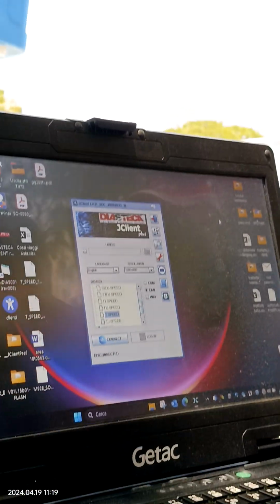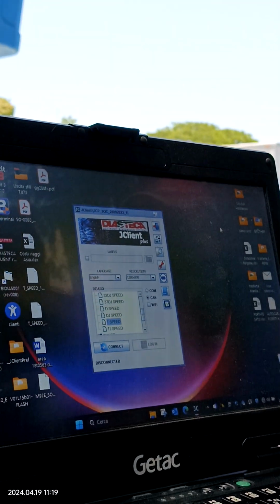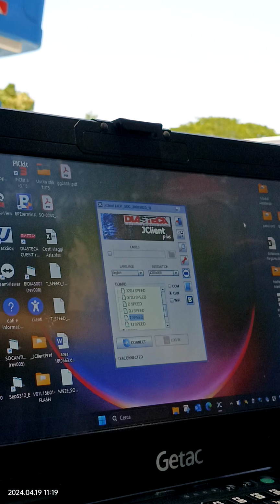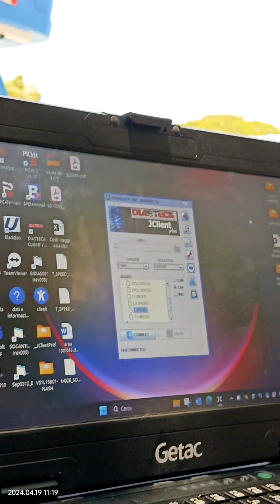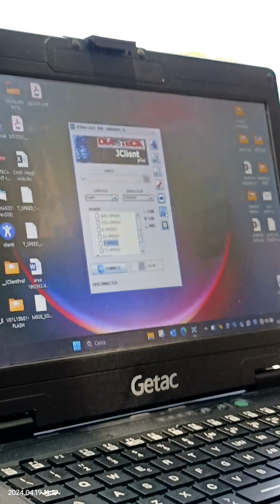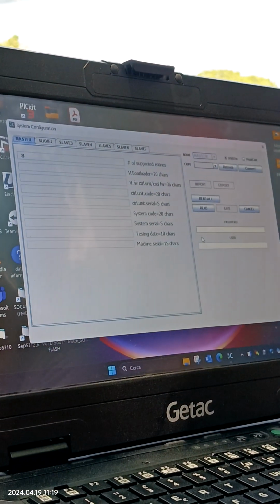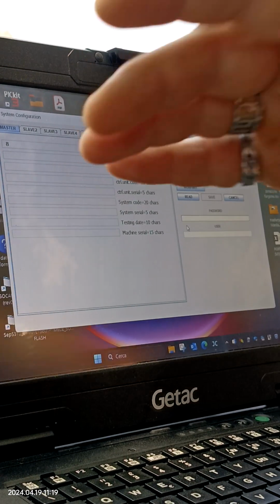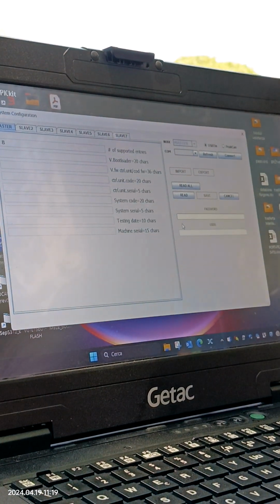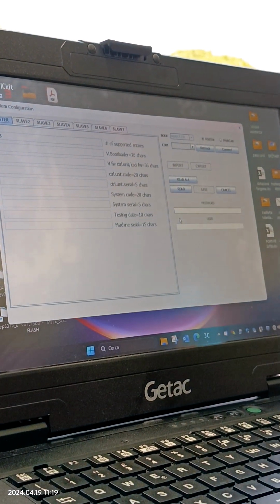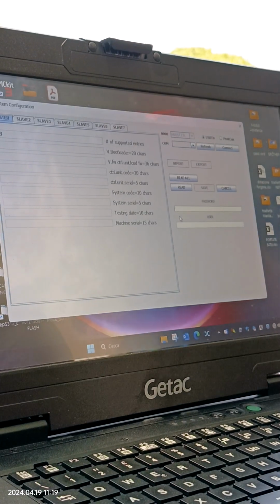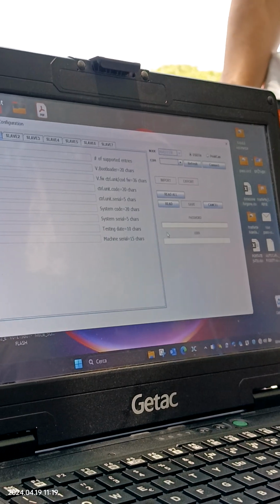Very important: turn off the electronic system, switch on again, and go to read whether the machine keeps the new firmware. In the file you have the complete name, and you compare whether the machine accepts this. It's difficult to explain, it takes one minute, okay, guys.